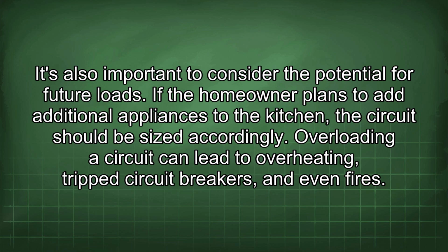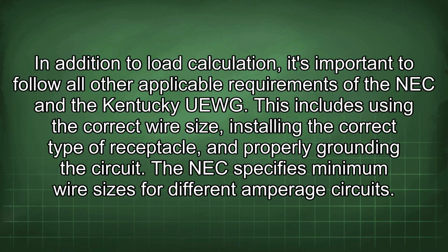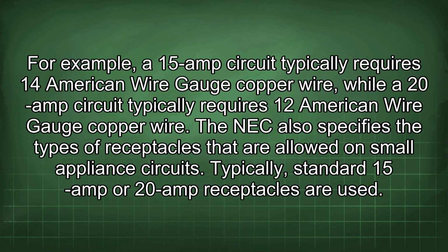Overloading a circuit can lead to overheating, tripped circuit breakers, and even fires. In addition to load calculation, it's important to follow all other applicable requirements of the NEC and the Kentucky UEWG. This includes using the correct wire size, installing the correct type of receptacle, and properly grounding the circuit. The NEC specifies minimum wire sizes for different amperage circuits. For example, a 15 amp circuit typically requires 14 American wire gauge copper wire, while a 20 amp circuit typically requires 12 American wire gauge copper wire.